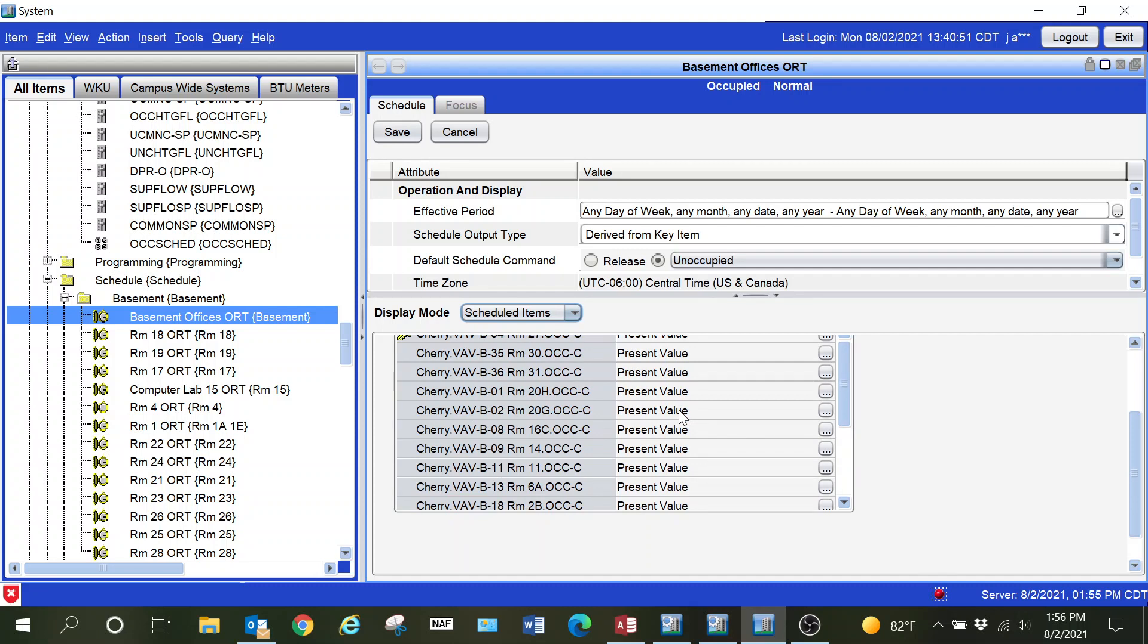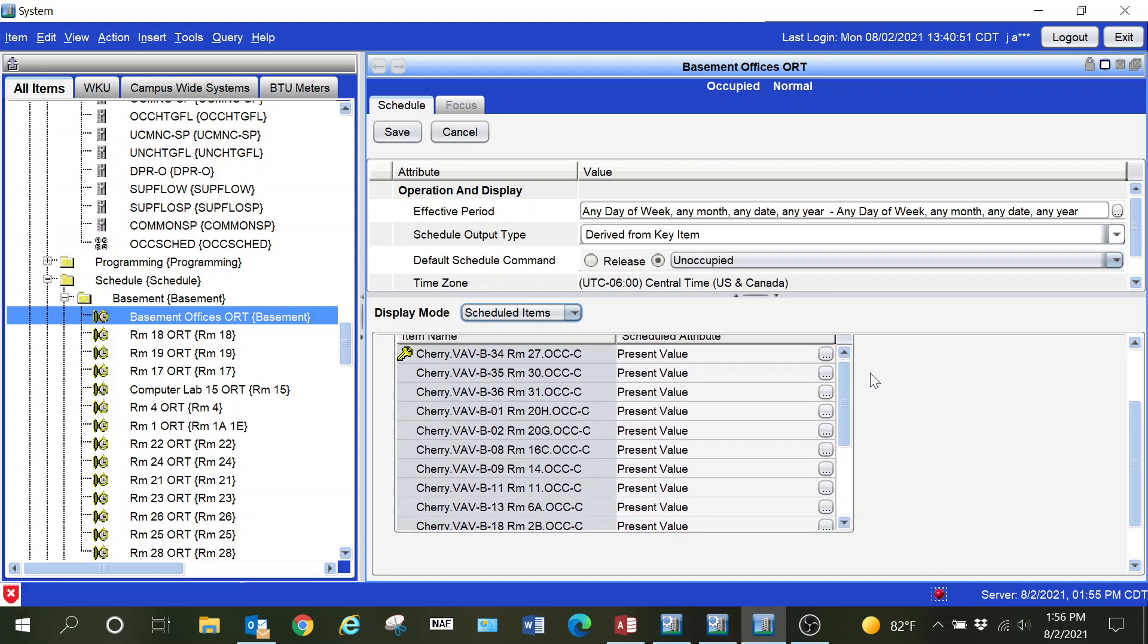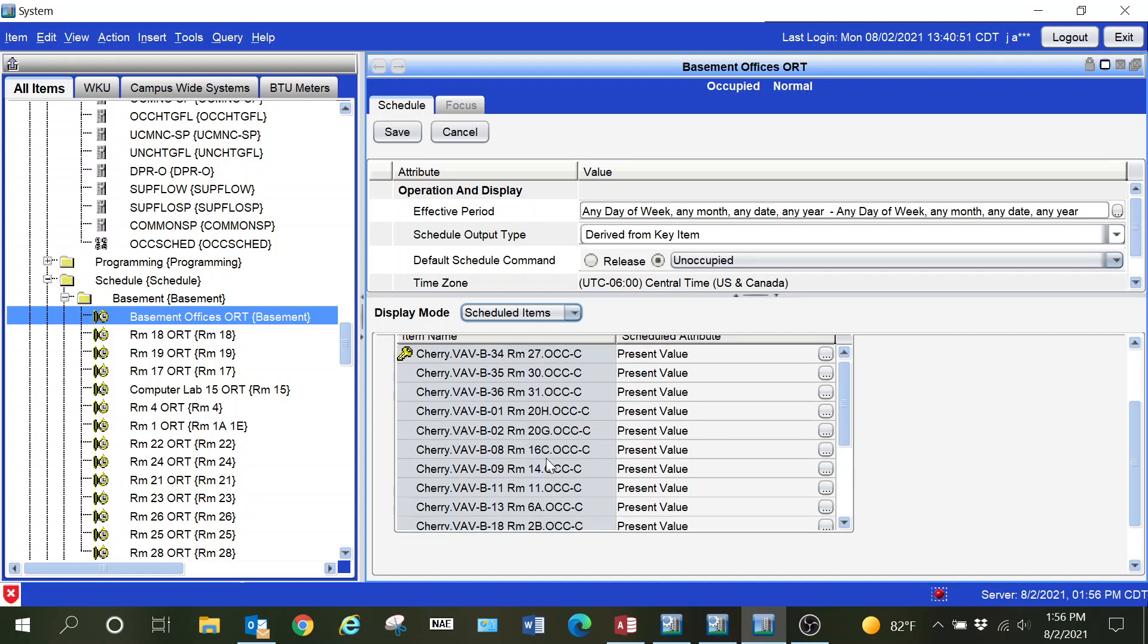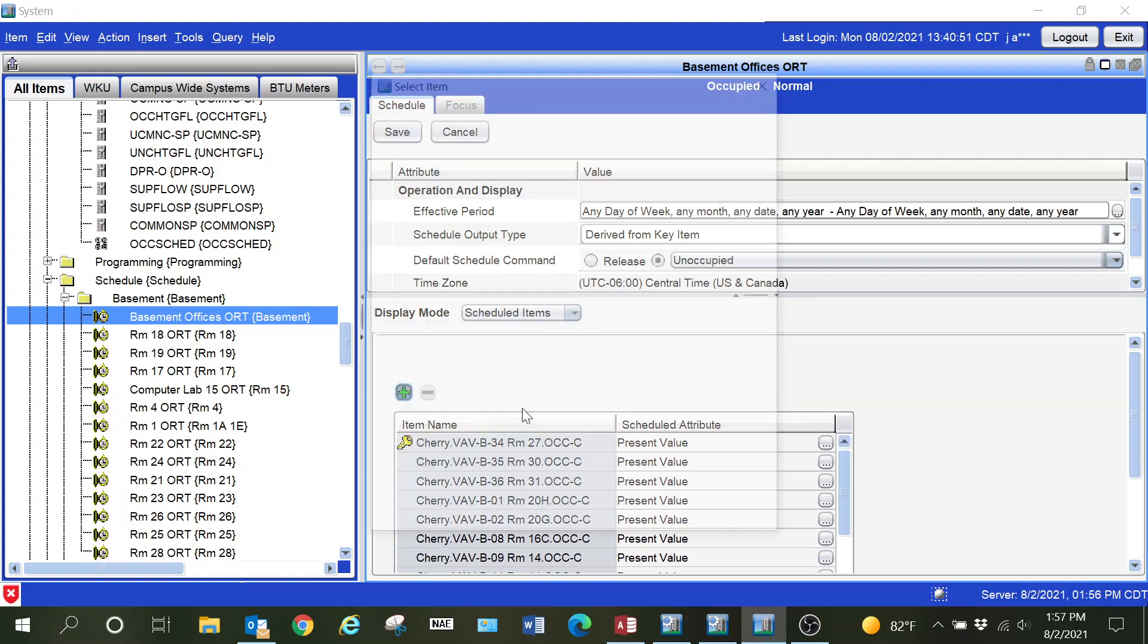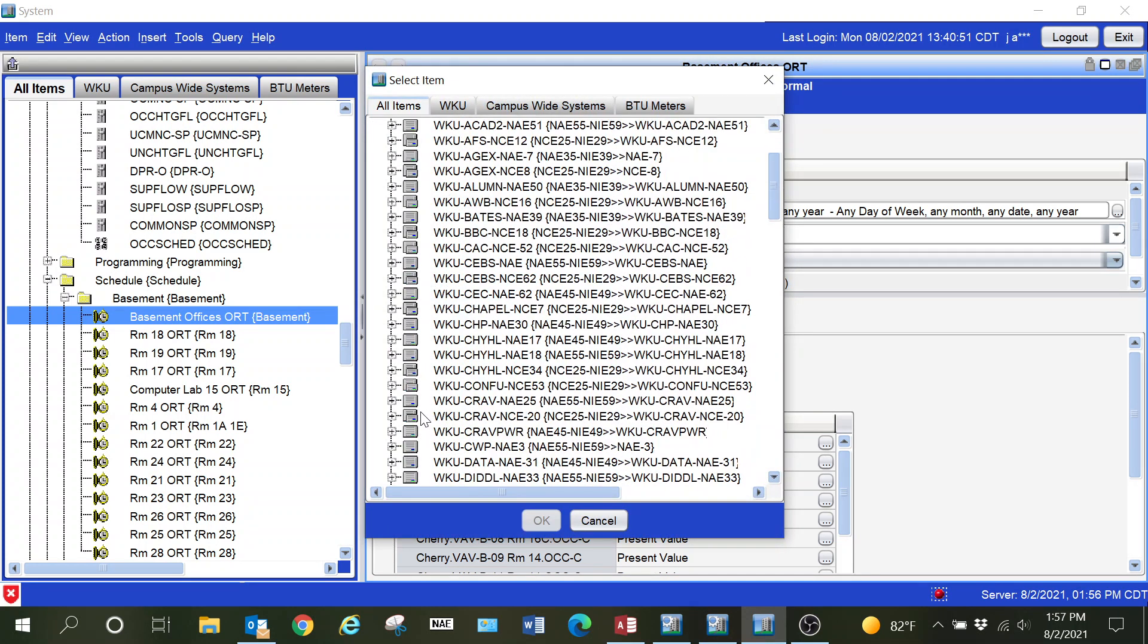You can see here that the particular occupancy point for that box, the original box in the schedule, is now out of range. It can't recognize it because it was a completely different device. Even though the address was the same, that point, that instance ID, all of that is completely different. You're going to need to go through your schedules and any kind of logic and make the corrections.